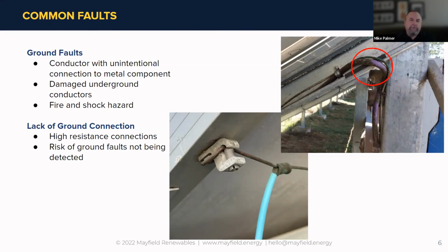Yeah, when we're in the array, many times we see this kind of thing, but what sticks out here is dissimilar metals, and over time that leads to a corrosion path. Even in this picture you see a crimped-on lug, and what Ryan talked about being drilled into the frame of the module. All those are points that can become open at some point and not be the ground you thought they were.